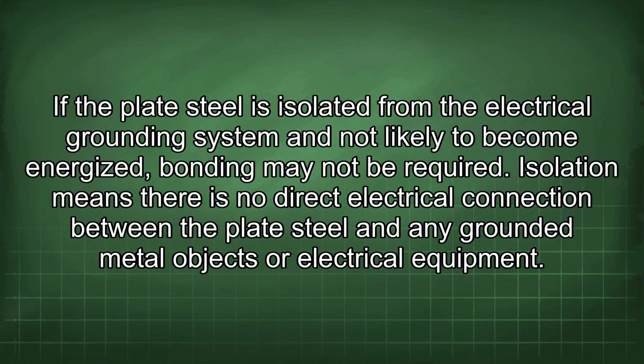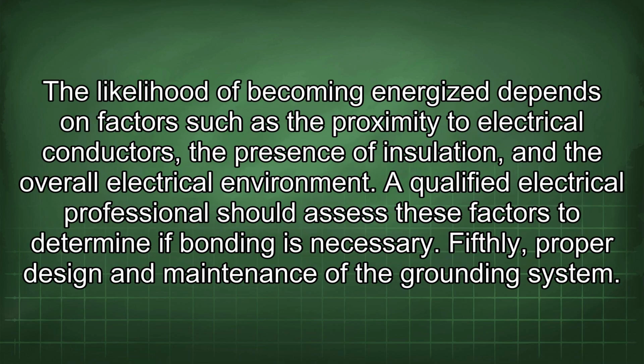Isolation means there is no direct electrical connection between the plate steel and any grounded metal objects or electrical equipment. The likelihood of becoming energized depends on factors such as the proximity to electrical conductors, the presence of insulation, and the overall electrical environment. A qualified electrical professional should assess these factors to determine if bonding is necessary. Fifthly, proper design and maintenance of the grounding system.